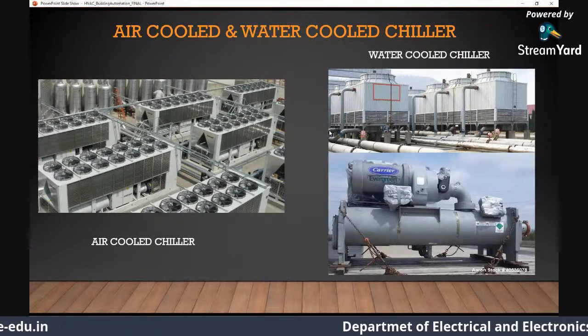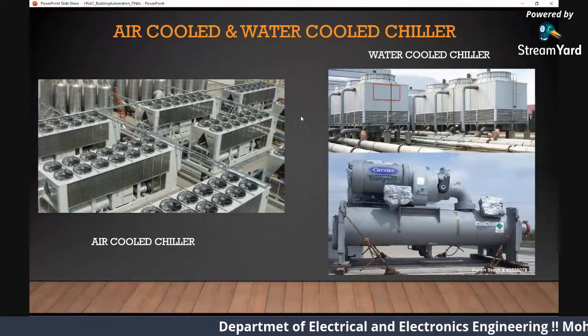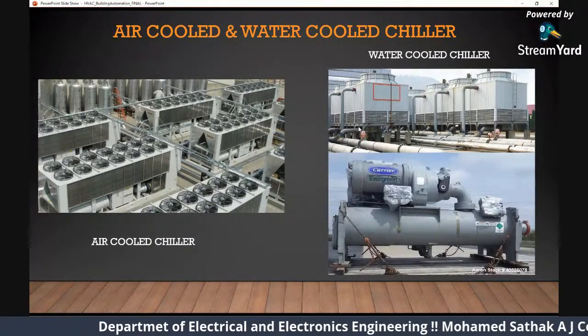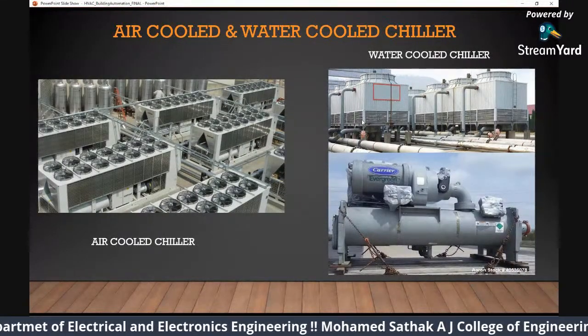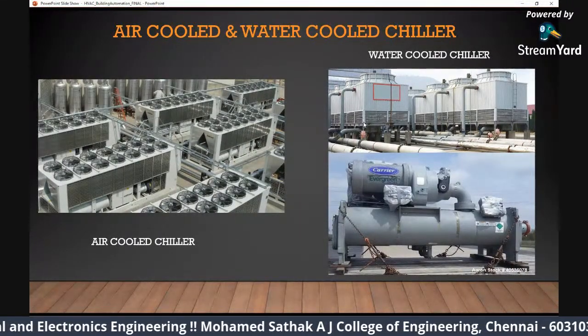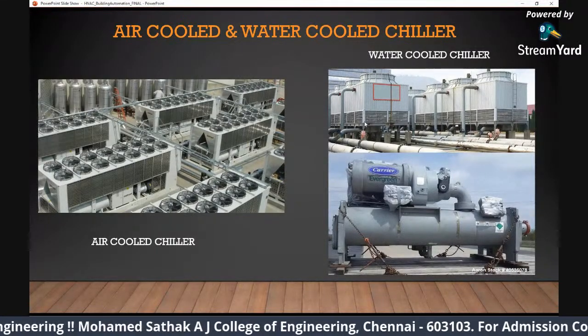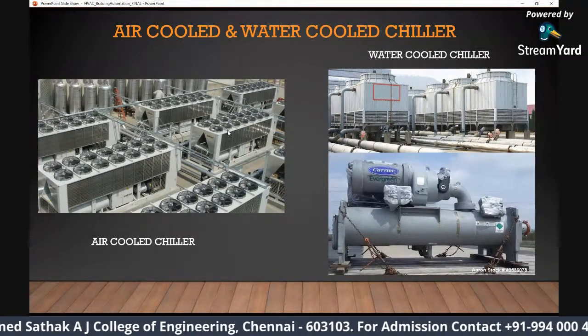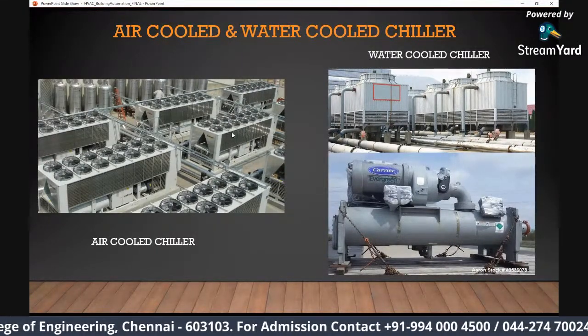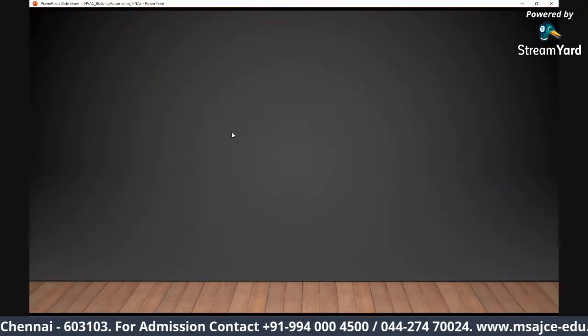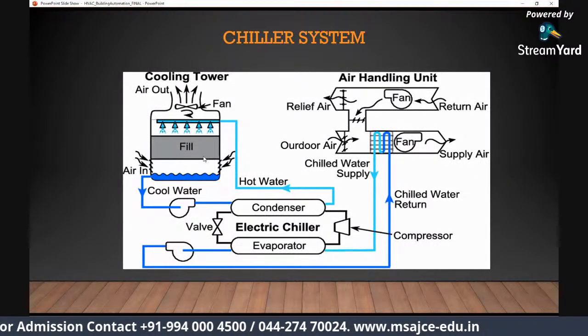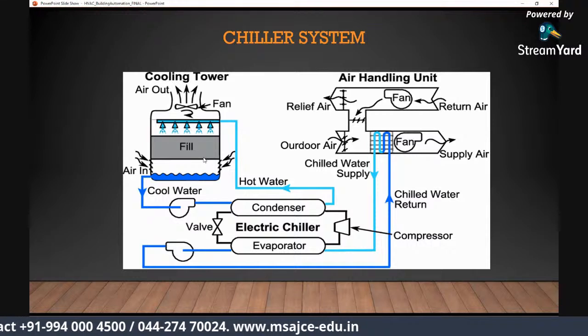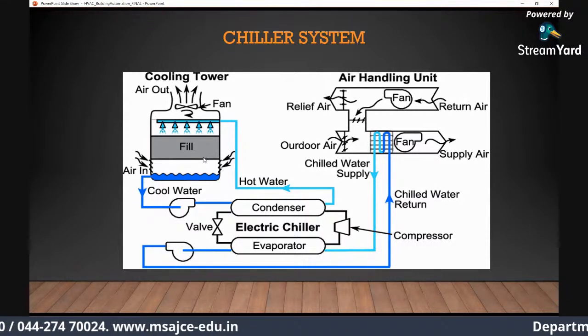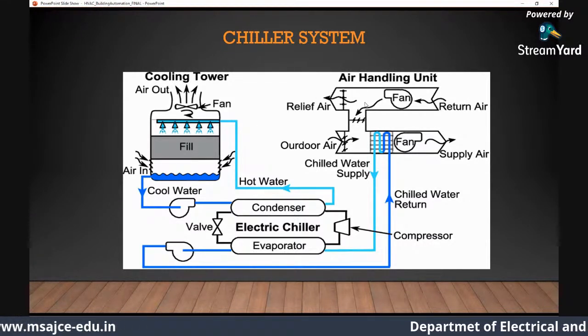And in a water cooled chiller, you use cooling towers to cool it. Instead of the fans, we use water to cool your refrigerant, but there will be a fan in the cooling tower too, along with the water, not just fans. I'll explain in detail. There's a beautiful picture on the next slide which tells you the whole difference. This is a sketch representative of a chiller or a cooling system completely in detail. I'll take you part by part.